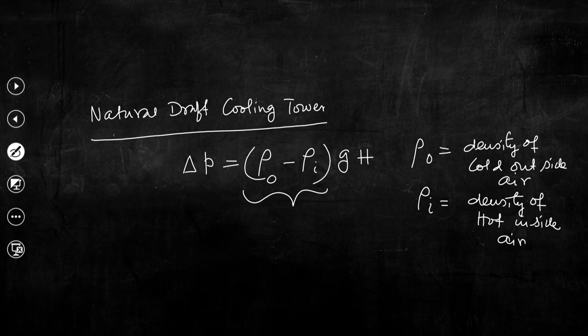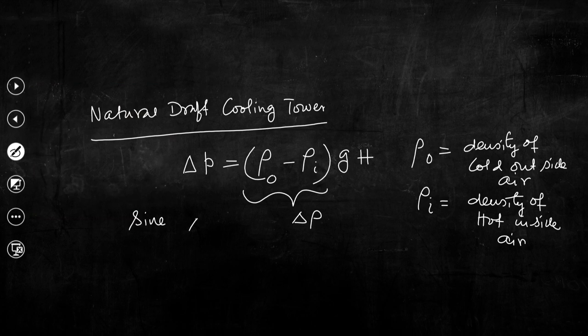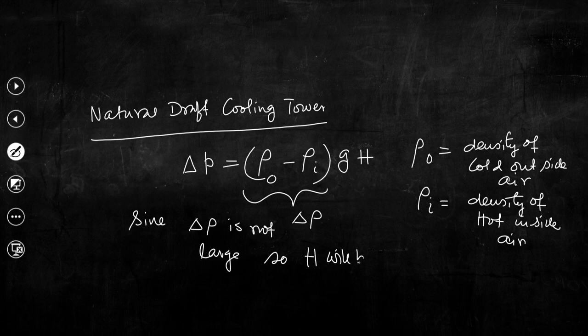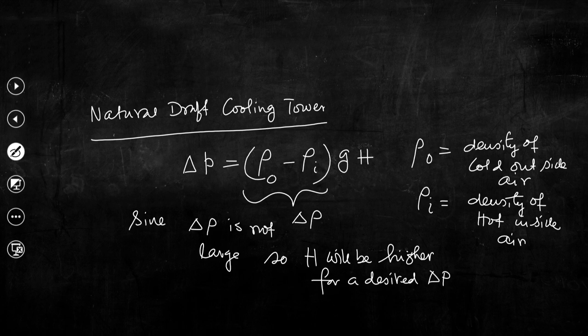Air has to flow over this particular arrangement where it experiences substantial resistance because of the fill structure. To overcome that resistance and maintain a certain flow rate of air, the pressure difference must be sufficient. Since the density difference is not very much — the density of cold air and hot air are close — what we need to do in a natural draft cooling tower is make H very large to get a sufficient value of delta P. That is why natural draft cooling towers are very tall.